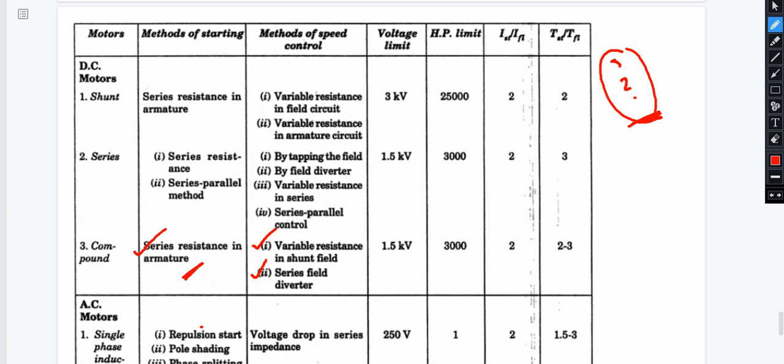The voltage rating is 1.5 kV with 3000 horsepower. Starting current is 2 times full load current. Starting torque is 2 to 3 times full load torque depending on the type of compounding — differential compounding or cumulative compounding. The magnitude of compounding affects the performance characteristics.